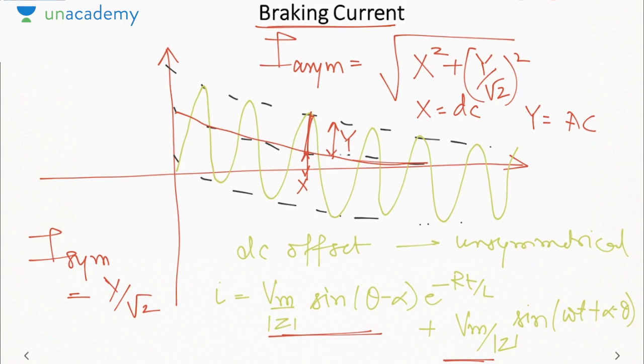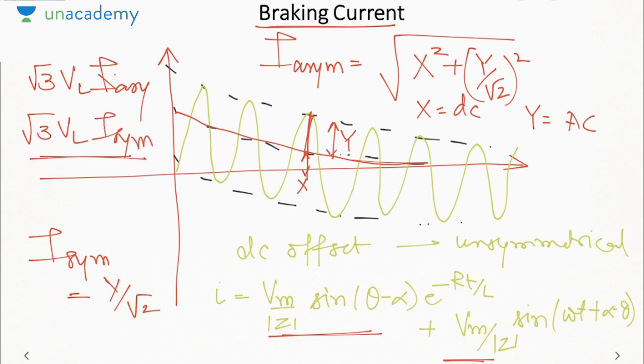Okay. And if we want to find the power, the breaking capacity will be root 3 VL into I. If you take the symmetrical current, it will be called the symmetrical breaking capacity. If you take the asymmetrical current, it will be called the asymmetrical breaking capacity. You just have to multiply root 3 VL into I asymmetrical for the asymmetrical breaking capacity, and root 3 VL into I symmetrical for the symmetrical breaking capacity. So these are the two currents defined in terms of the breaking current of the circuit breaker.